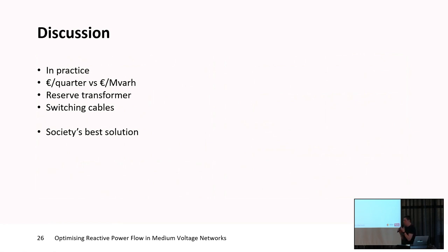So what does this mean in practice? For the DSO, they have to measure at the interface with the TSO the exchange of reactive power and act on that value. It also requires some measurements in the grid, and of course this can be done with state estimation, for example, and a couple of measurements. And of course we have to look at society's best solution.